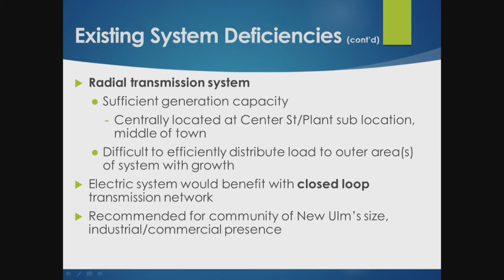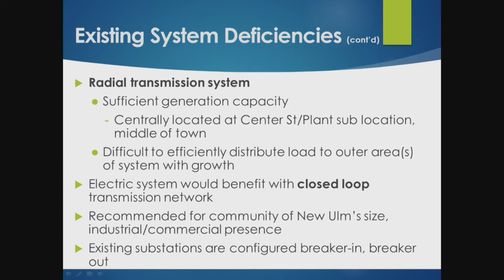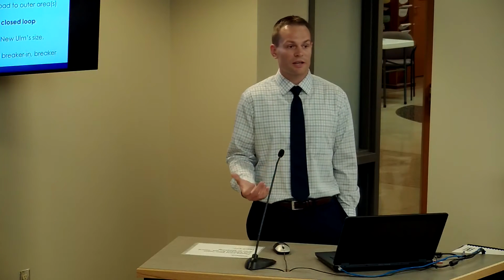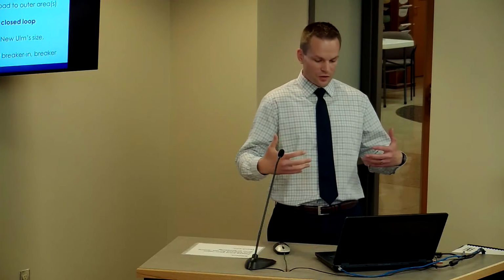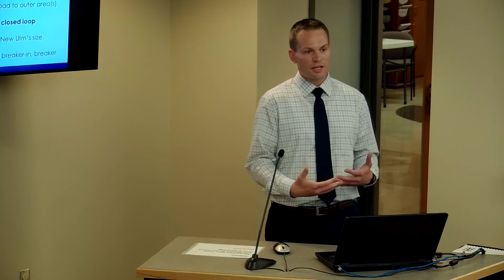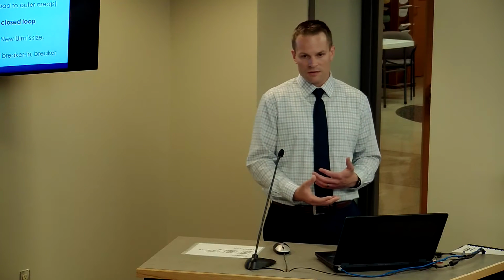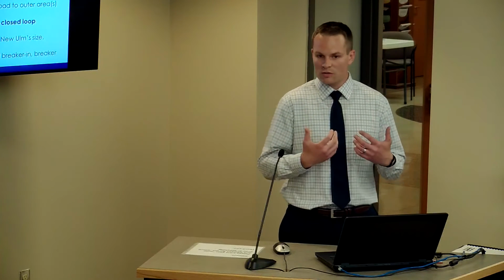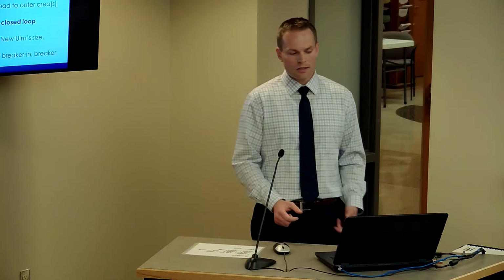You can obtain a closed loop system, and that looks really good when you do have a transmission outage. At most you would see a blink, but if it's a closed loop system, you're energized from two sources all the time. If a line goes down, a breaker opens, and you don't see any outage whatsoever.